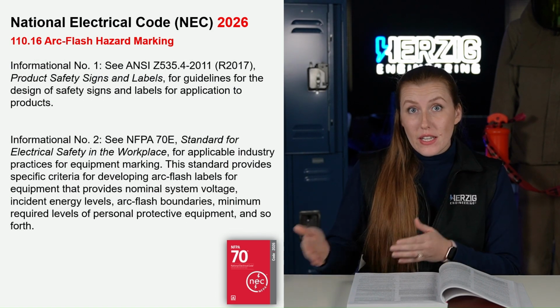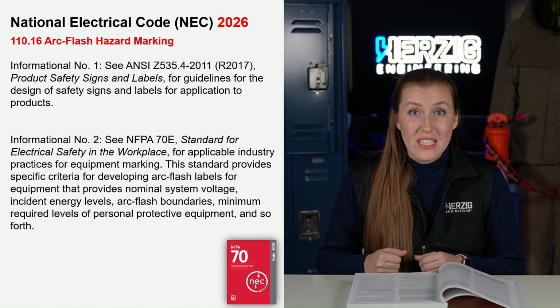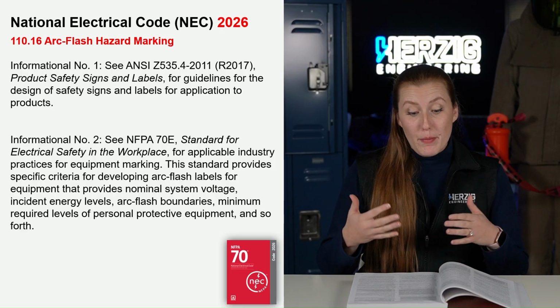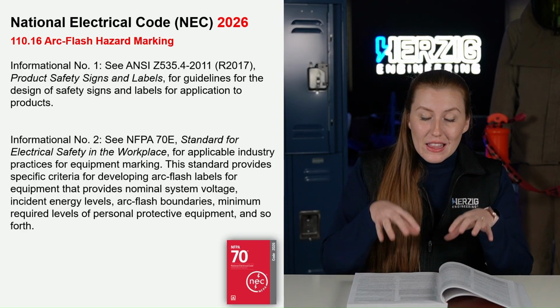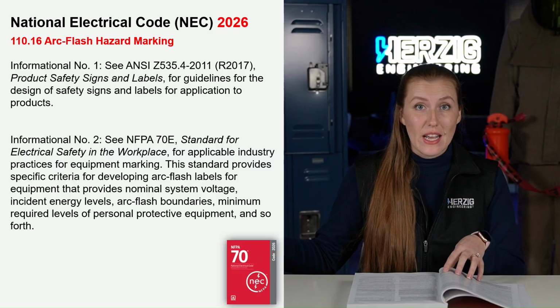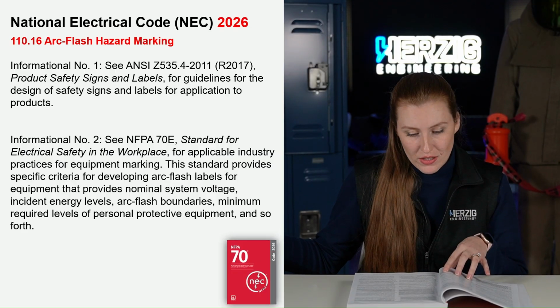What actually is this person going to be facing if they are exposed to those conductors or circuit parts? It does still, in the informational notes, point to the NFPA 70E for how to accomplish this, but it now more closely aligns in the code book with what the 70E has said for many, many editions. So it's great to see them expand this and clarify that generic labels on less than 1,000 amp service equipment, feeder equipment, is not acceptable.